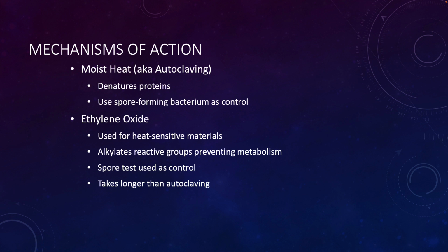Same thing with the ethylene oxide. We just expose the spores to the sterilant. And as long as they don't propagate after the procedure, then we know we're good.